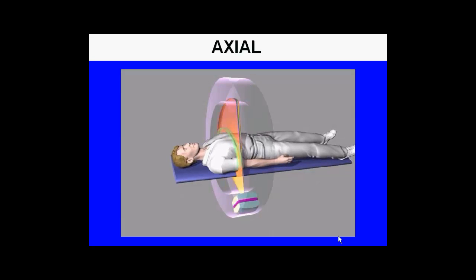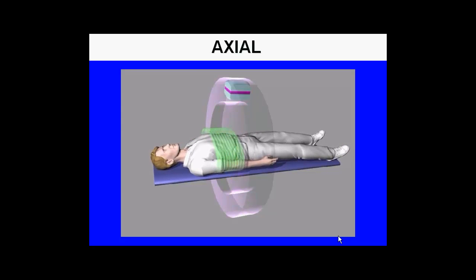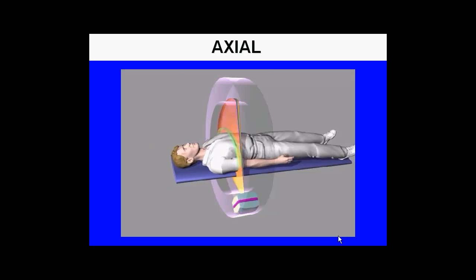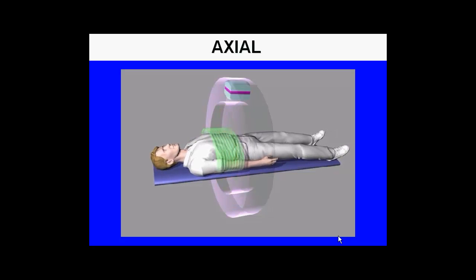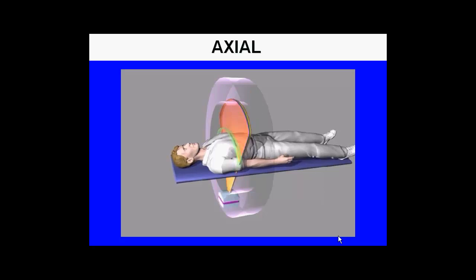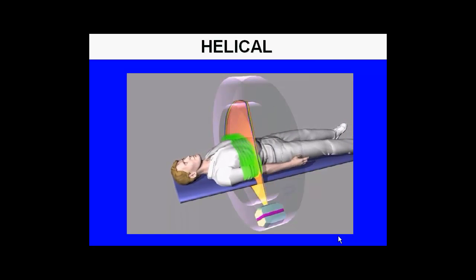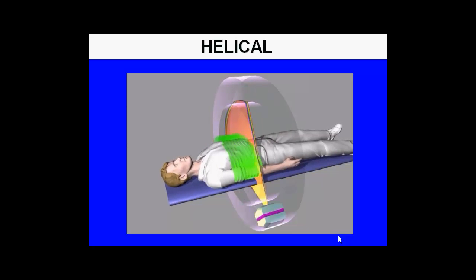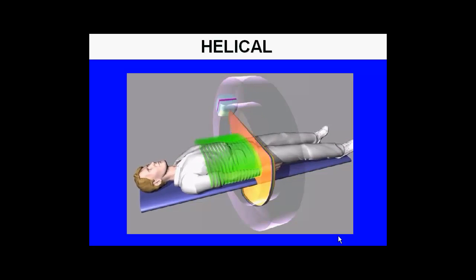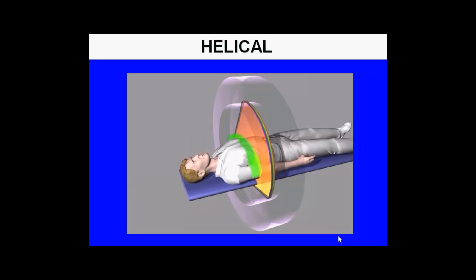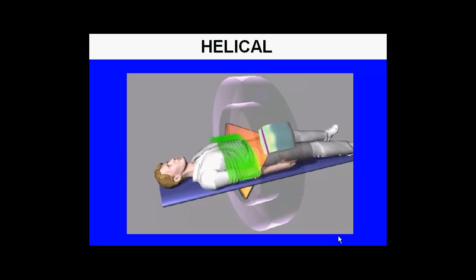In axial imaging, images are acquired each time the x-ray tube spins about the patient. Therefore the images are acquired in a manner of take a picture, move the table, take a picture. The helical mode basically continues to spin the camera about the patient while continuously moving the patient couch, thus producing information in a true helical or spiral manner, which is later reprocessed to parallel tomographic images.